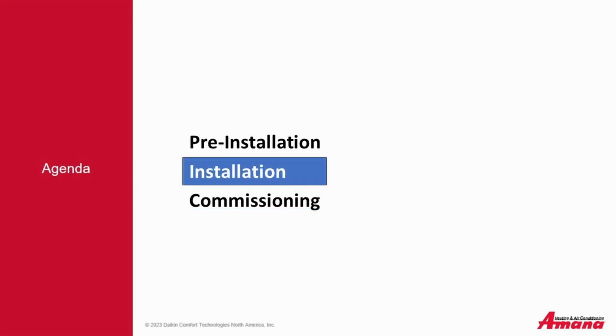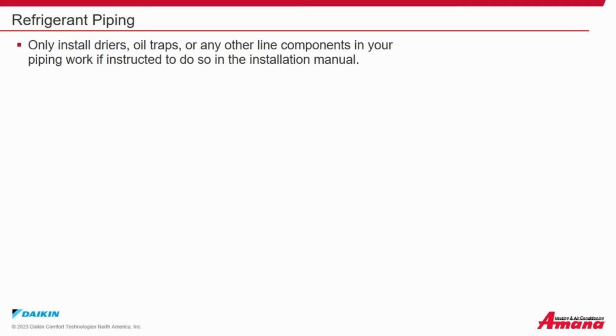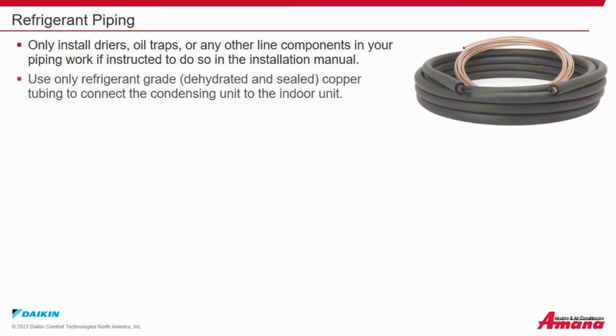Installation. Refrigerant piping. Only install dryers, oil traps, or other line components in your piping work if instructed to do so in the installation manual. Use only refrigerant-grade, dehydrated and sealed copper tubing to connect the condensing unit to the indoor unit.